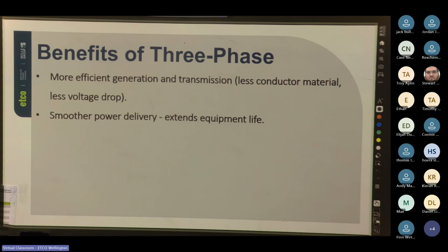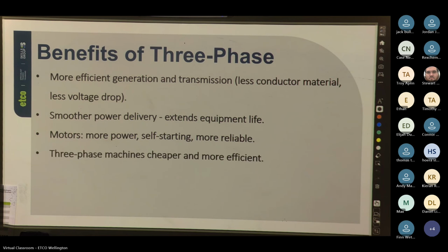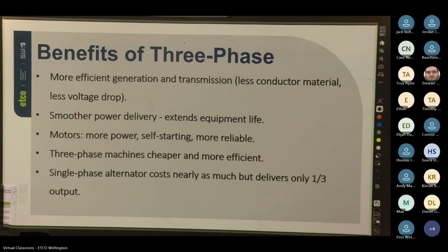Cool. We would have a smoother power delivery, so it extends equipment life because it's a much smoother. We don't have as much volt drop in the forward reverse direction. So for motors, we get more power, they're self-starting, and they're more reliable. So we don't have to use extra equipment to start our motors. And three-phase machines are generally cheaper and more efficient, so less power wastage. And single-phase alternators cost nearly as much, but deliver only a third of the output. The other thing with three-phase machines is if you can run all 3 phases relatively equal, you get charged less because you're wasting less power.